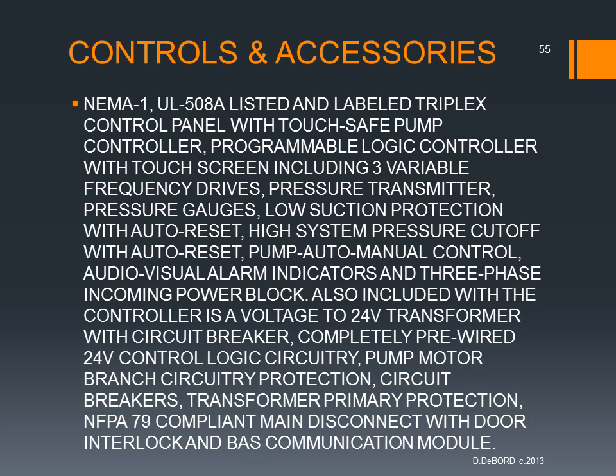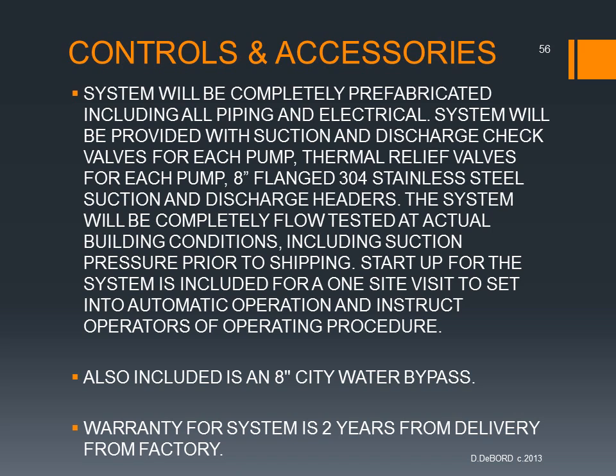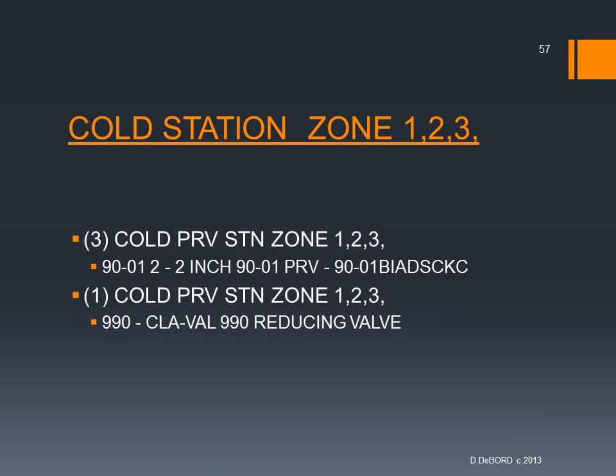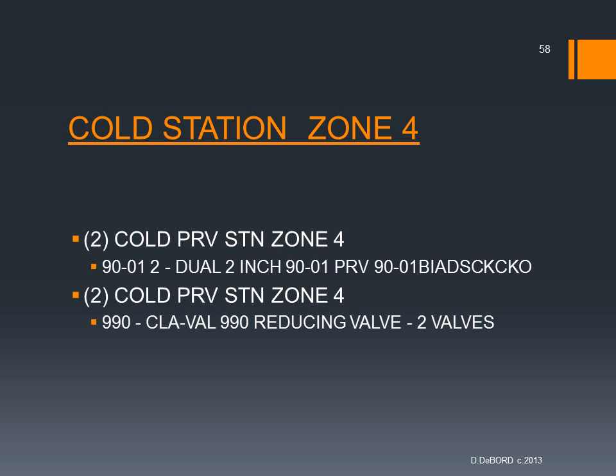Some of the controls and accessories. All this stuff needs to be specified. See a NEMA 1 cabinet. We don't want it to get wet. A few other details, warranty information. Then our PRVs. If you're feeding them both the same way, the cold water and hot water should have the same pressures. Sizes can be different depending on your loads, but the pressures should be the same because the zones are the same. And we want them to be balanced.